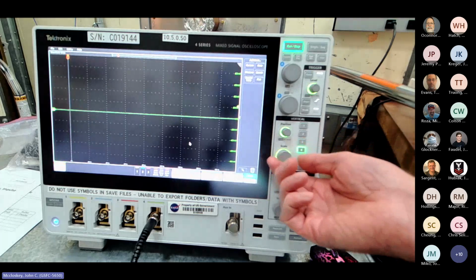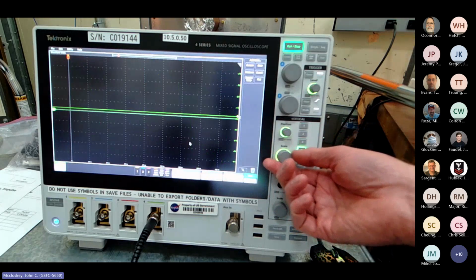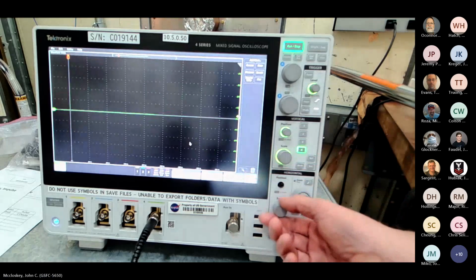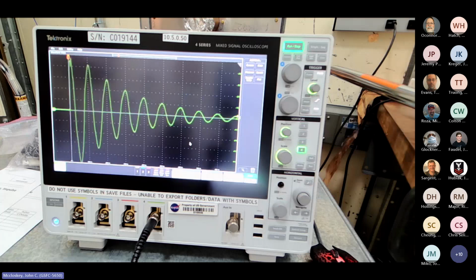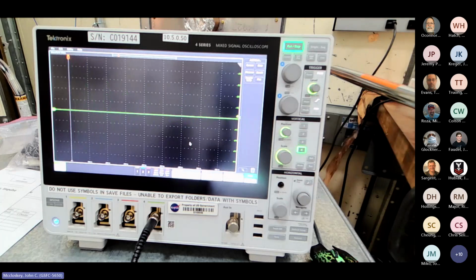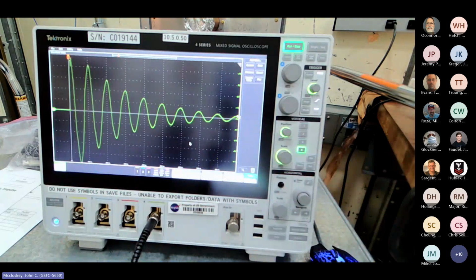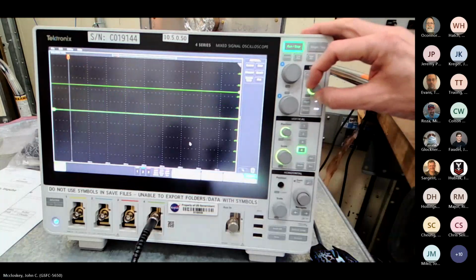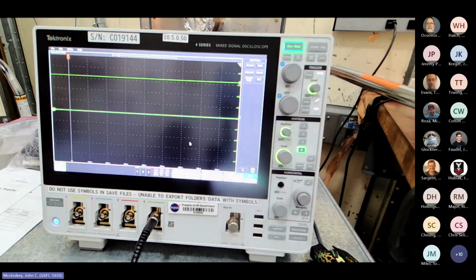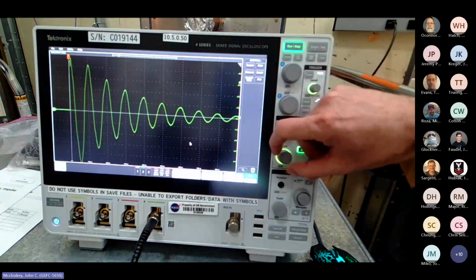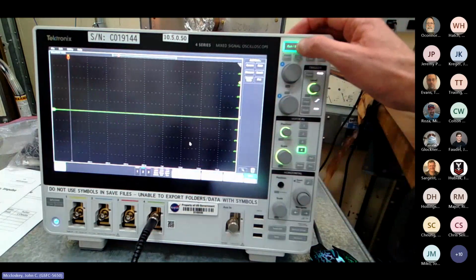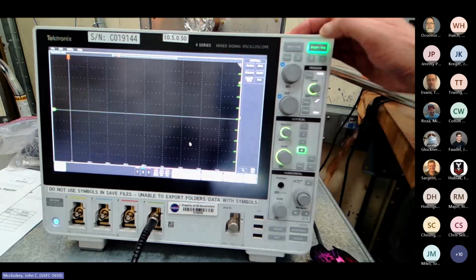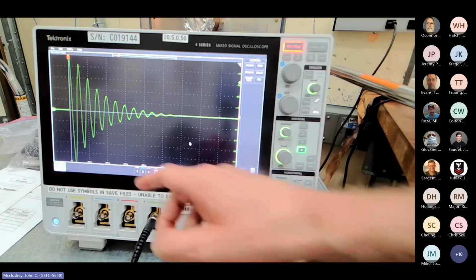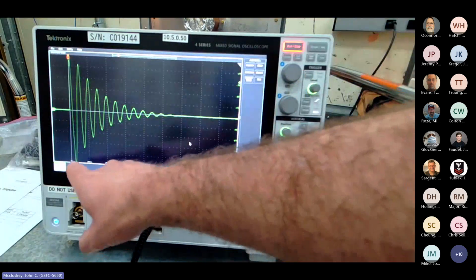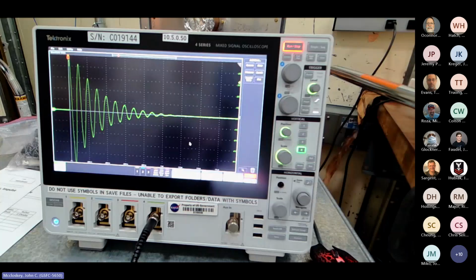So remember, 10 amps is the default for this signal. 10 amps into 50 ohms is 500 volts. Through the 40 dB of attenuation is 5 volts. Okay, and so now we're on 1 volt per division. And let's trigger. It was pretty low, so it's getting a lot of spurious stuff there. All right, so that's giving us a good trigger. Do a single trigger and then let it stop. Okay. So the peaks are coming right up to about 5 volts. So that's the limit that this scope will provide.